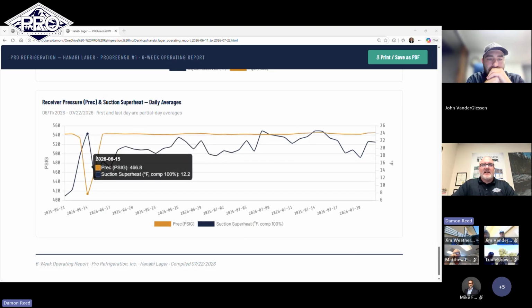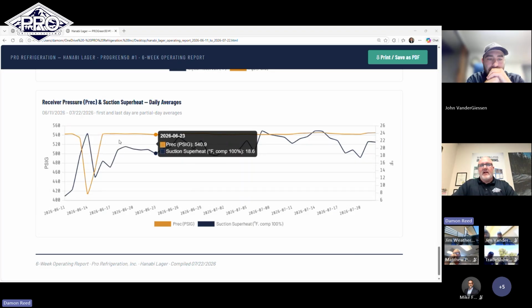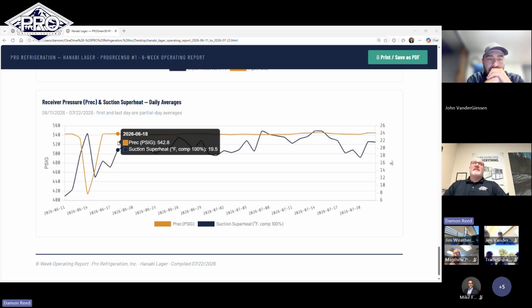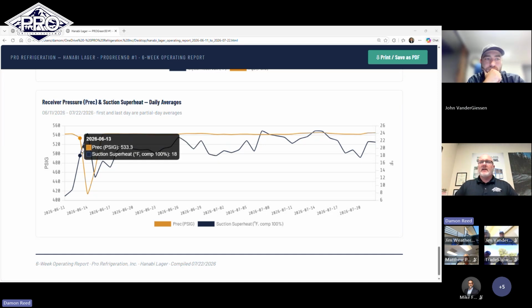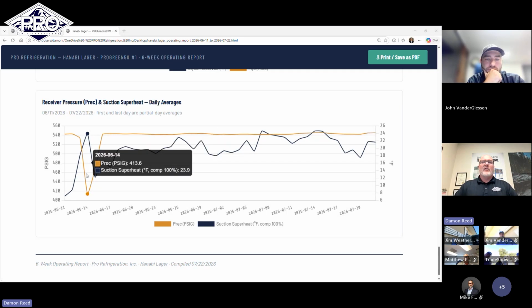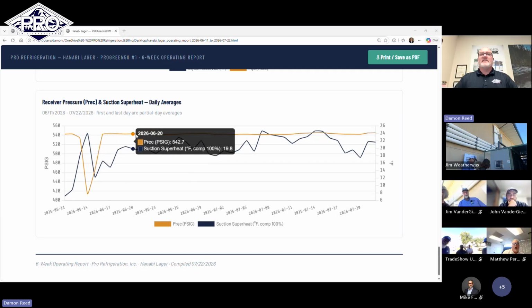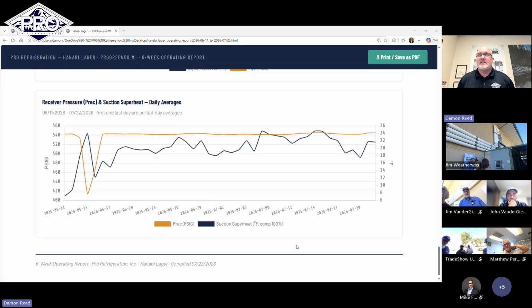Receiver pressure and suction superheat. One of the things, if you've heard anything about CO2 or people talk about CO2 systems, is that flash tank/receiver stability is a big important factor. And you can see once we get our service repair, our receiver pressure, which is the orange, I'll get my cursor out of there, is staying pretty stable. So that's a good stabilized system. The suction superheat has variability, but that's just with cycling and things like that.